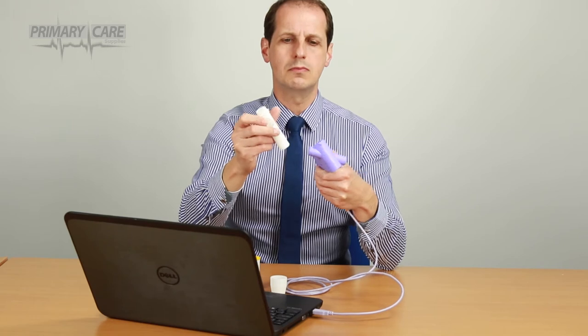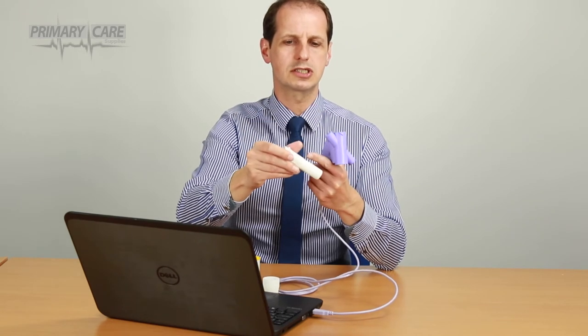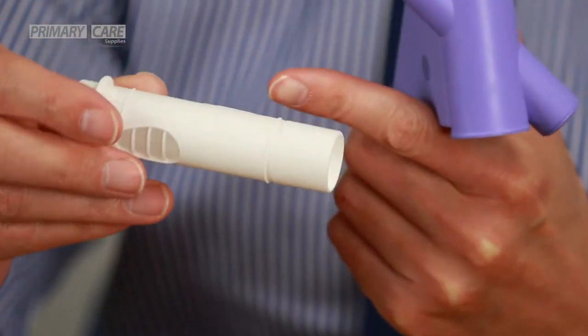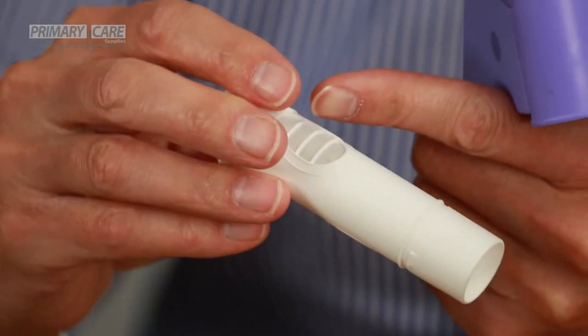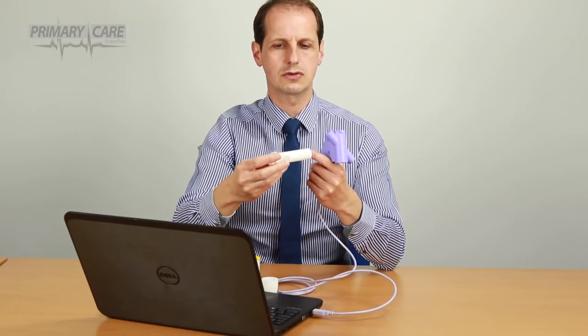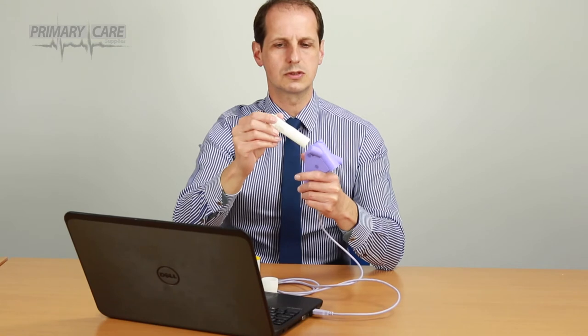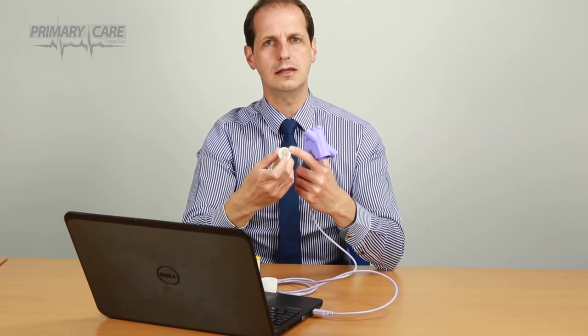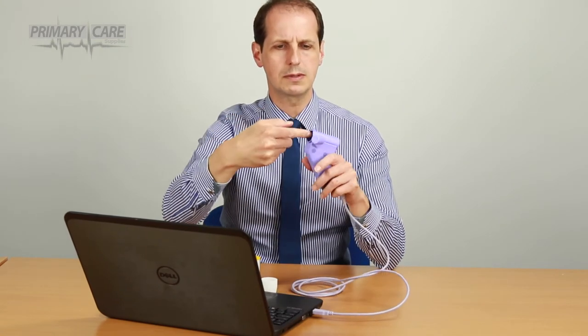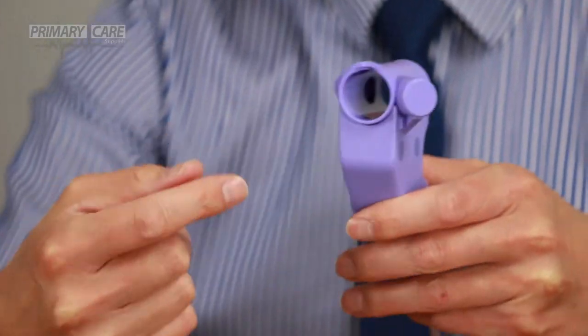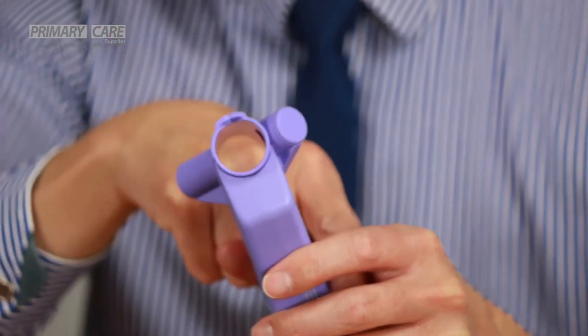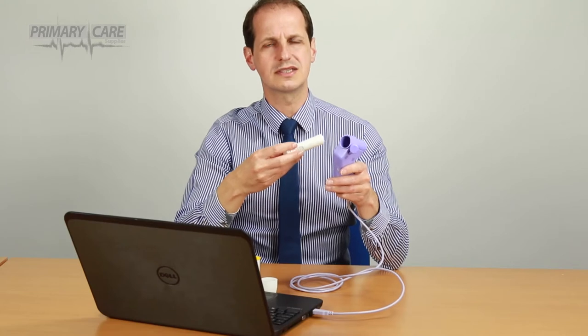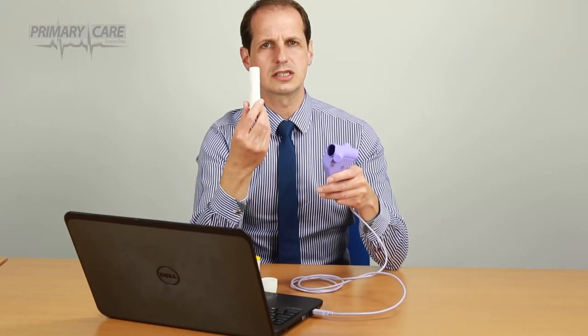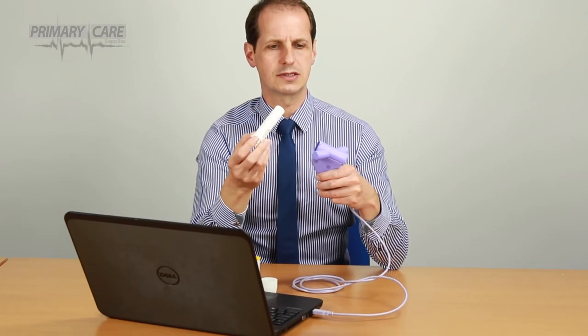The Spirette M would go into here. Now on each side of the Spirette M is a window. Now in that window is a filter. So where the sound passes through, there's a filter, which means anything that's inside here, i.e. the patient's breath, will not come into contact in here. So for cleaning, you can just wipe the outside of this down with a sterilising wipe and change the Spirette M on a weekly basis.